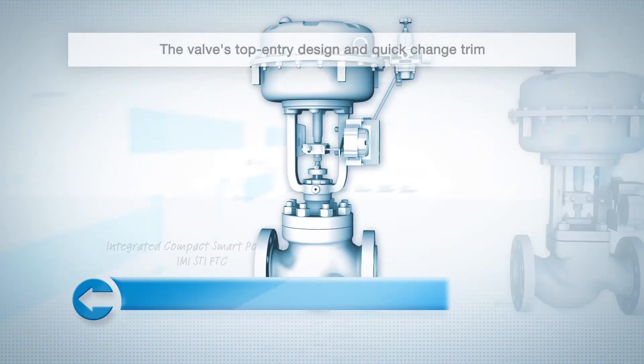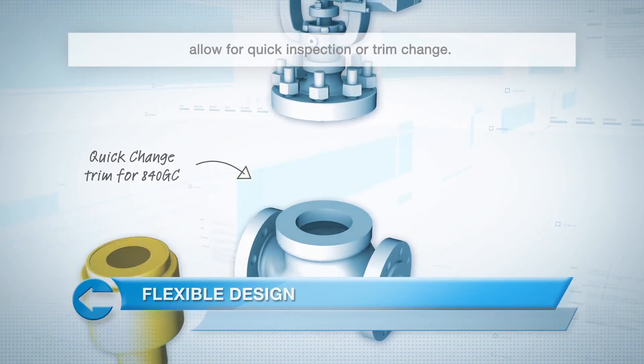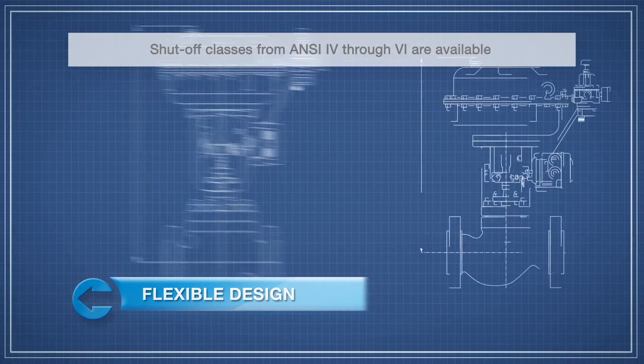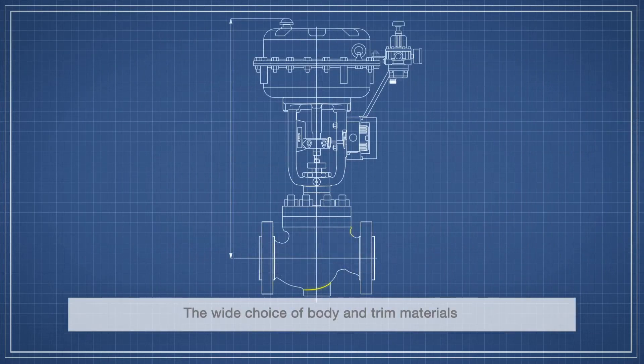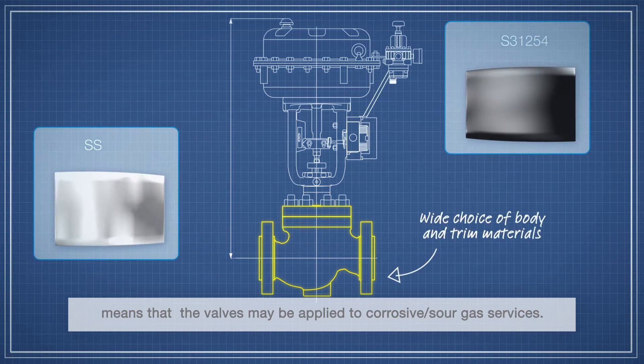The valve's top-entry design and quick-change trim allow for quick inspection or trim change. Shut-off classes from ANSI IV through VI are available to meet application requirements. The wide choice of body and trim materials means that the valves may be applied to corrosive or sour gas services.